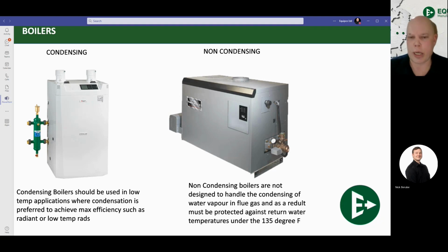That leads us to our non-condensing boilers, where we're going to have cast iron heat exchangers and copper heat exchangers. These things are not designed to handle anything acidic. So if we put acidic condensate over top of these burners, over top of these heat exchangers, it is going to eat through those heat exchangers. It's not going to happen in 24 hours or anything like that. But over time, depending on how much condensate you're creating, you will cause a leak in this heat exchanger. And if the leak is caused by condensation, it will void the warranty. You will not get warranty on that heat exchanger.